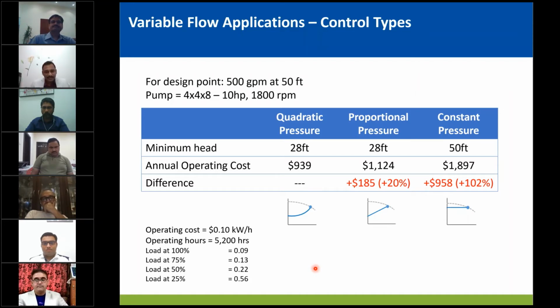Now, this is an example worked out, 5,200 hours and 10 cents a kilowatt hour. If you look at the dollar savings, and the size of the pump, it's just 10 HP. So if you have a bigger pump in place, and you implement a proper control strategy from day one, it would save so much energy that it will pay for itself in under two years.